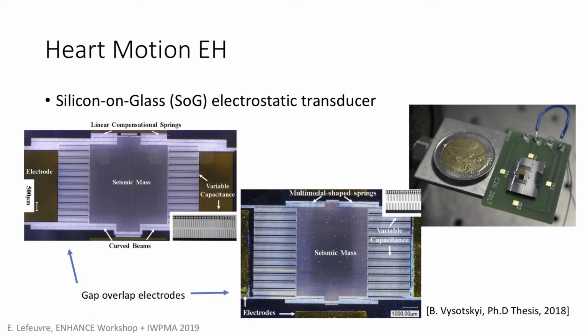So I'll show you a few devices. So that's the device with bistable and linear compensational spring, and you can see the difference in size with multimodal, what we call multimodal. It has exactly the same characteristics in terms of force displacement, but it's much smaller. And we have the same kind of electrodes. It's called gap overlap, and it's a forest of very thin fingers. So we have a lot of them, and maybe the only tricky point is to make sure that in the only photolithography we have, we have all the fingers perfect, no defect, because we don't want the mobile part to be stuck with the fixed one.